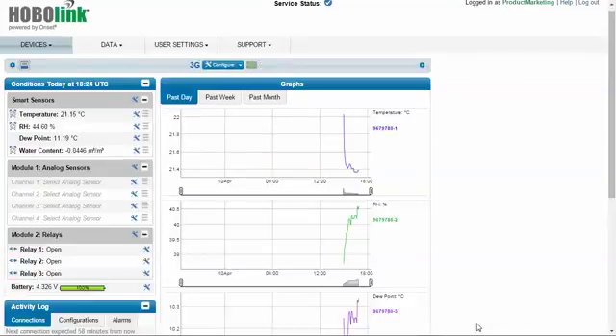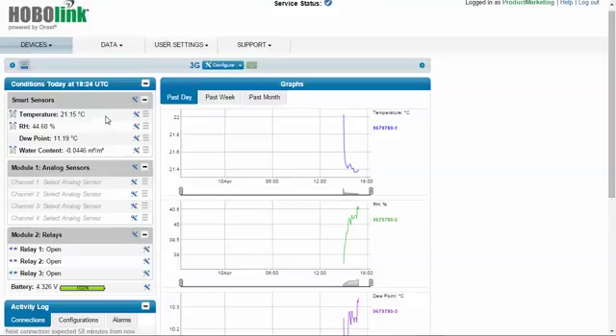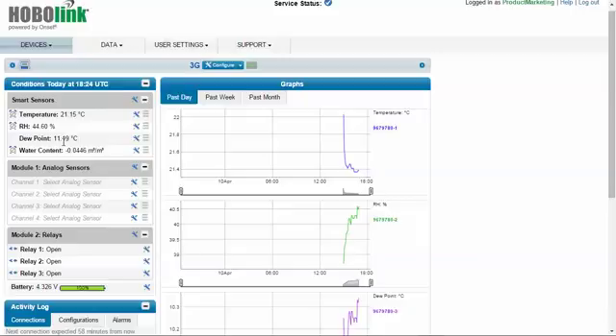Once the RX 3000 connects to HoboLink, the sensors are recognized and listed in the smart sensors here. Here we see we have a temperature and relative humidity sensor connected as well as a calculated dew point from those two measurements. We also have a soil moisture sensor attached as well. And we can see that our next connection is expected in 58 minutes.